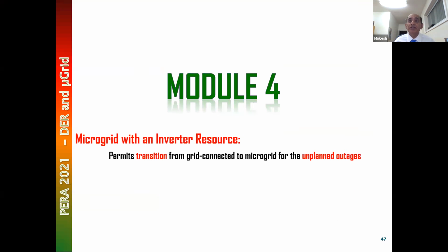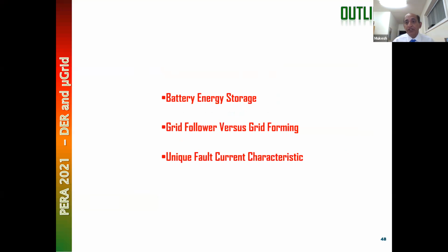with conventional sources. So this microgrid is formed by battery storage, and what I'm going to talk about is the battery storage system, which is the basis of this microgrid. And there's a grid follower versus grid forming mode in which the control system of this battery operates. So the battery as an inverter operates either in a grid follower mode or grid forming mode. Then I'm going to share with you the last part. I'm not sure if all of you have seen the unique fault characteristics of an inverter-based resource. That's what I'll share with you.